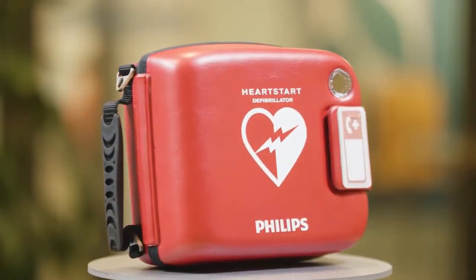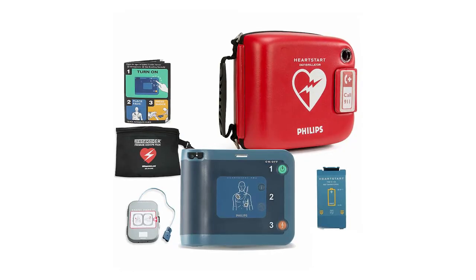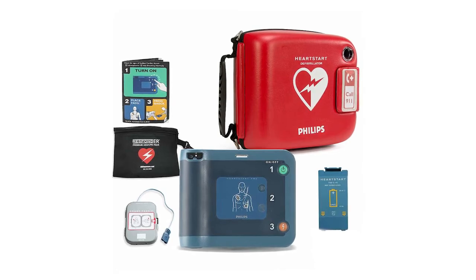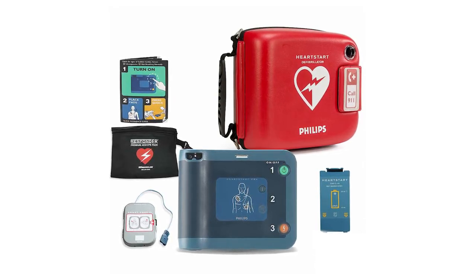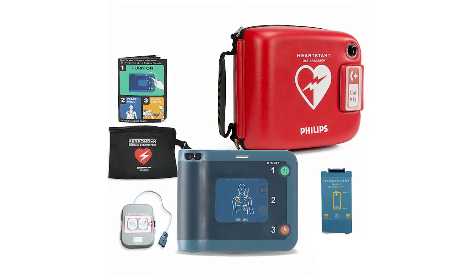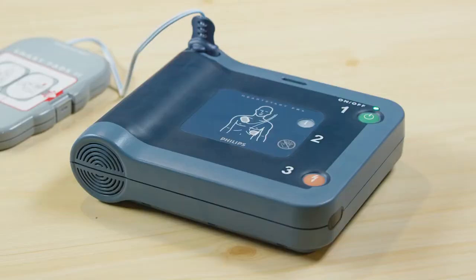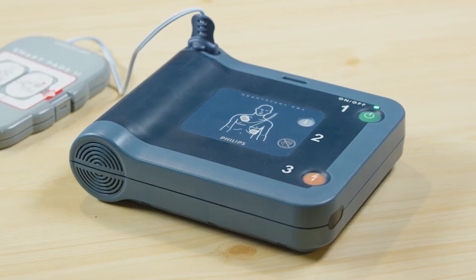Philips is the industry leader in AED devices. The package includes the HeartStart FRx device, battery, one package of smart pads, the owner's manual, and a quick reference guide. The HeartStart FRx performs a daily self-check to ensure all systems are operating properly. No manual calibration of the device is required. As long as the green ready light is blinking, the device is ready for use.